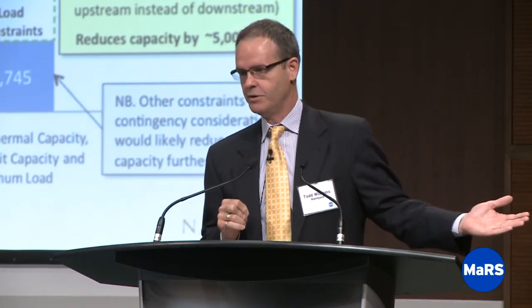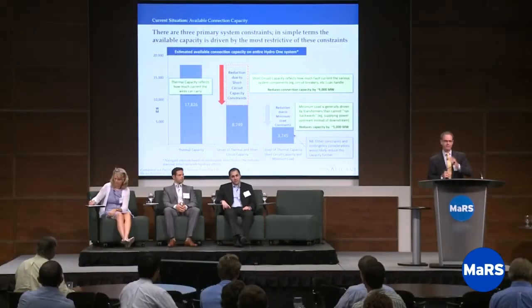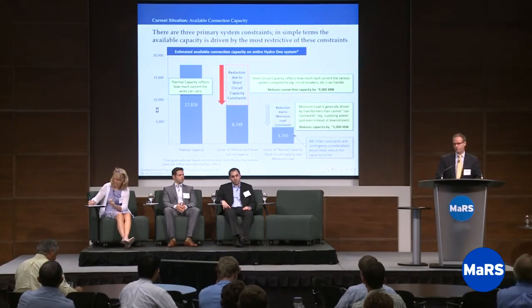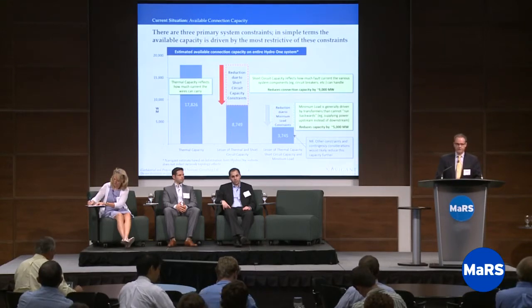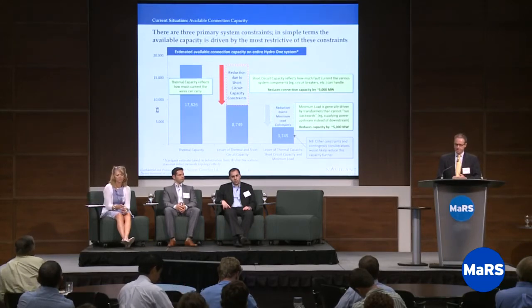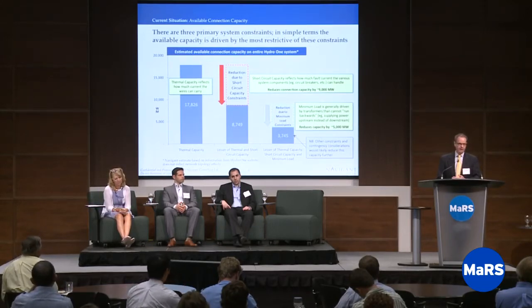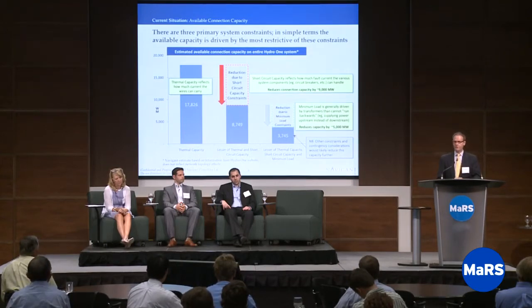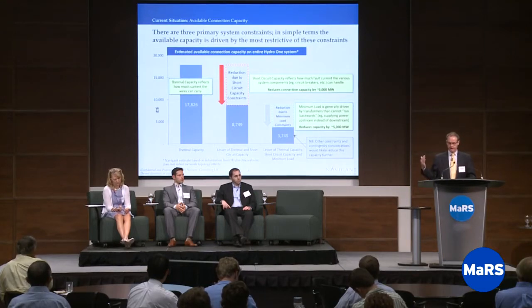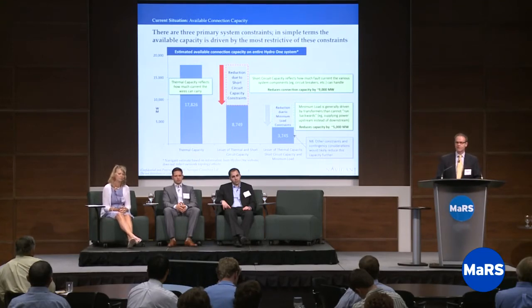In some cases, if you put too much in at the low end, you're going to ask the transformers to operate in reverse, and many transformers aren't built for this. So there's a reliability and possibly a safety issue. That constraint, minimum load, not letting transformers run backwards, costs you another 5,000 megawatts. So what started as a thermal capacity of about 18,000 megawatts gets constrained by two factors, one related to short circuit and another related to minimum load, and you end up with just under 4,000 megawatts of connection capacity.